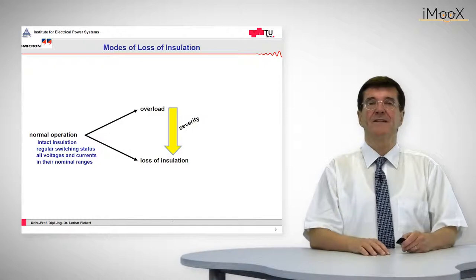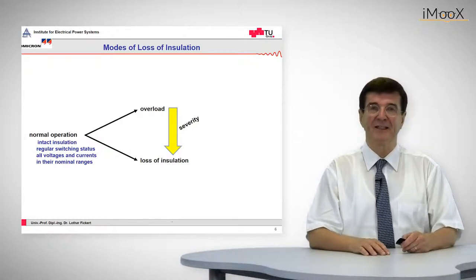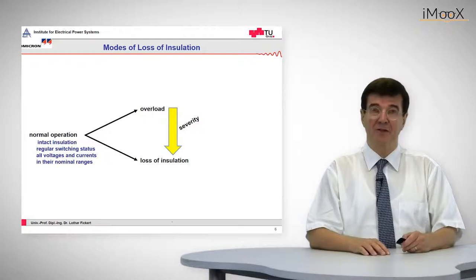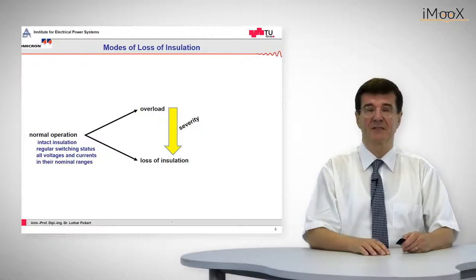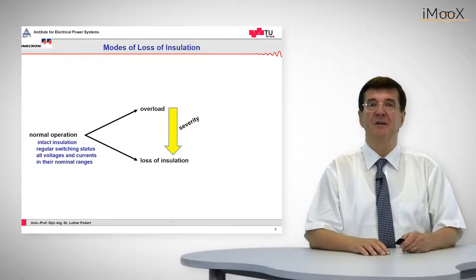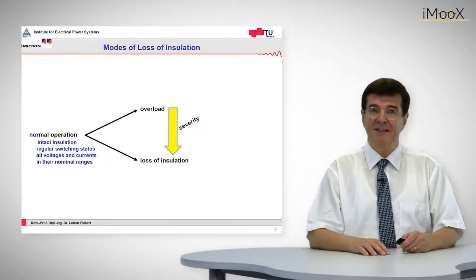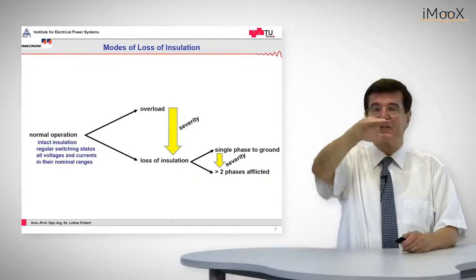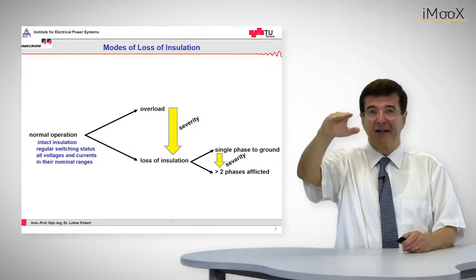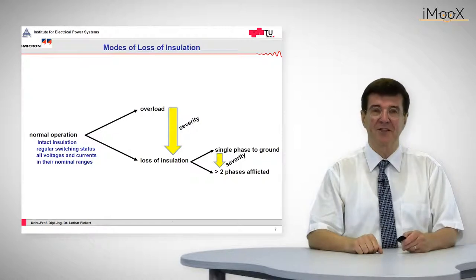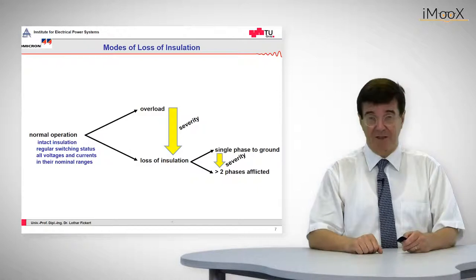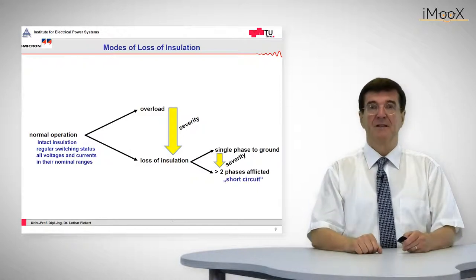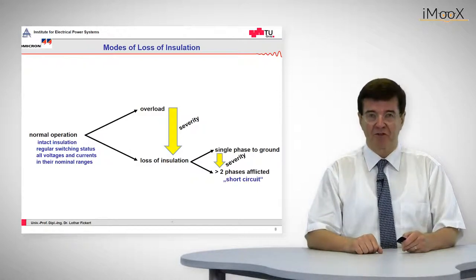So when these current-wise conditions are violated, then we speak either of overload or, in the case of loss of insulation, about short circuits. Overload means that the current goes slightly above the nominal current level and then is reduced. Whereas in the loss of insulation we have either a single-phase to ground fault or a multiple-phase to ground fault, which are also called short circuits.